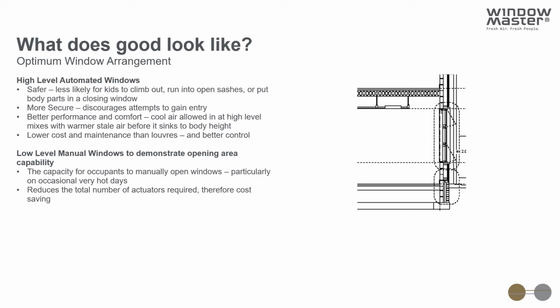So what does good look like? Based on our experience, we like to look at high-level automated windows, potentially with low-level manual windows underneath. These may very rarely need to be opened, but on very still summer days, we might want to use those windows to increase the opening areas to move air through the space. The majority of the time, however, the automated high-level windows will do most of the work at relatively small openings based on the airflow we can generate using wind speed against the facade.